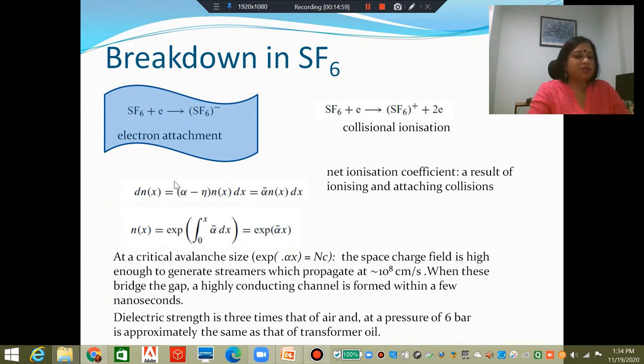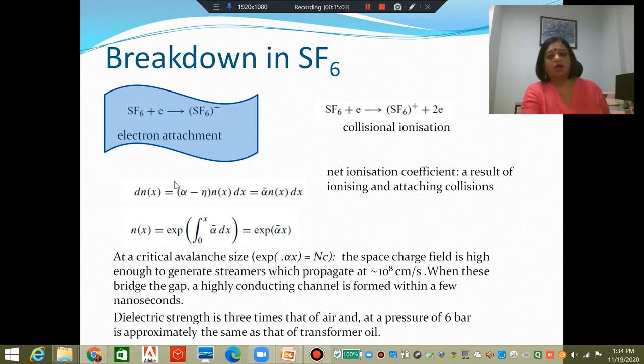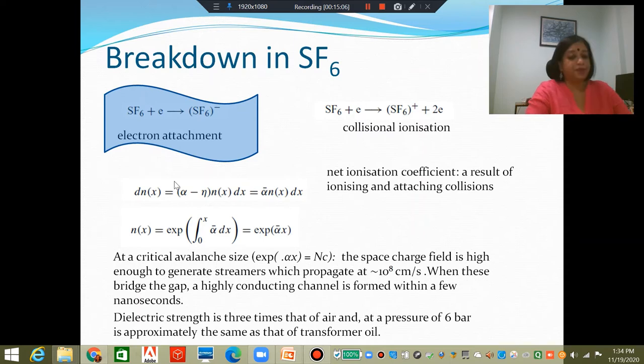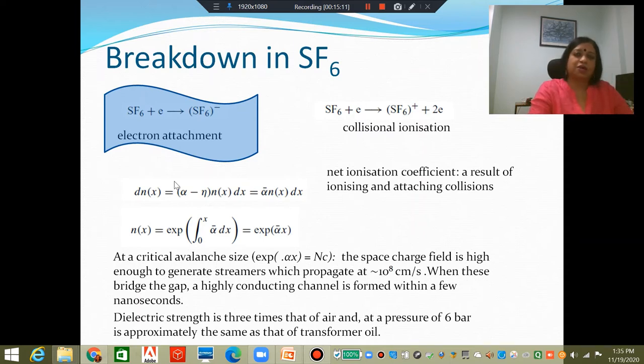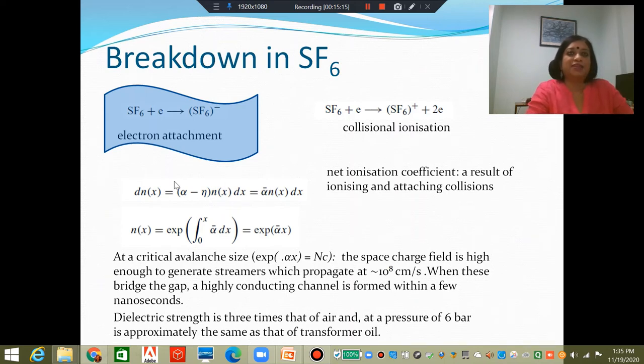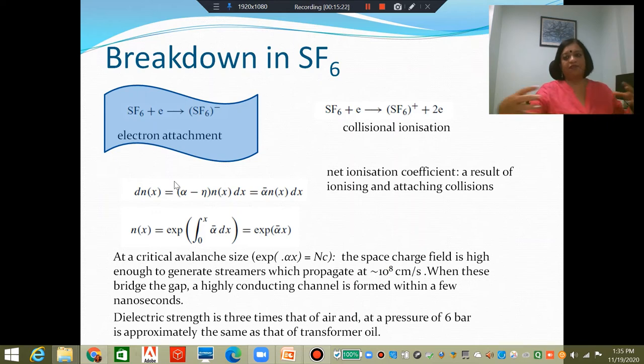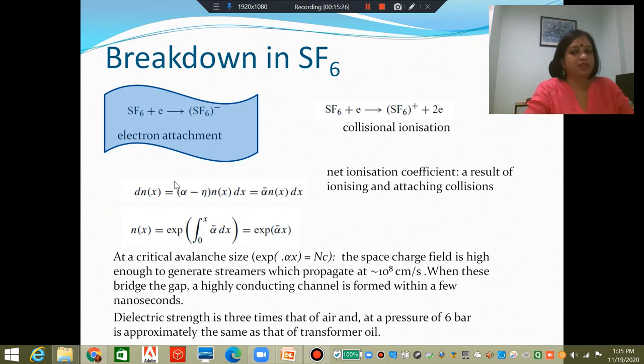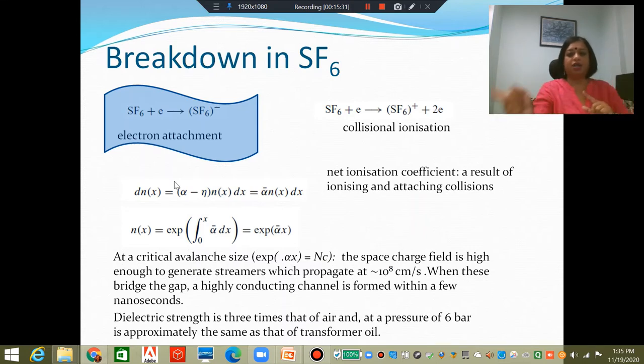Mostly in SF6, it is not Townsend's breakdown that causes breakdown. Rather, we see streamer breakdown. Townsend's breakdown can give rise to streamer breakdown under certain conditions — specifically, a critical density of space charge has to be satisfied.